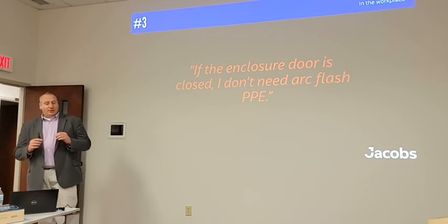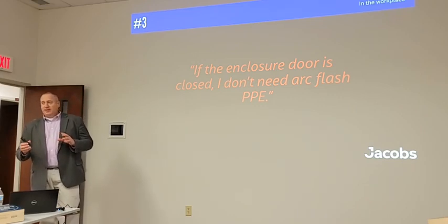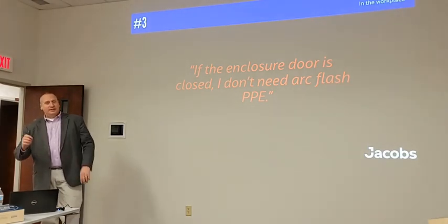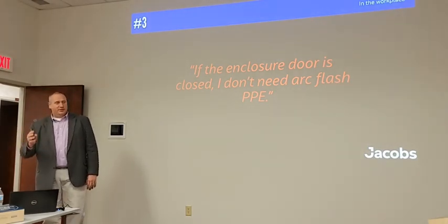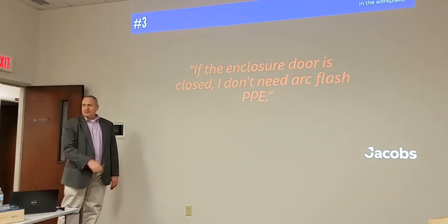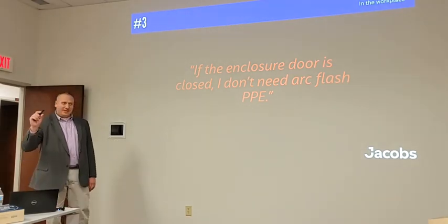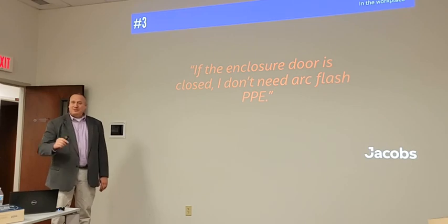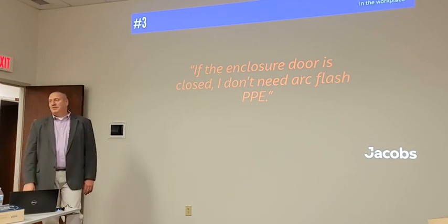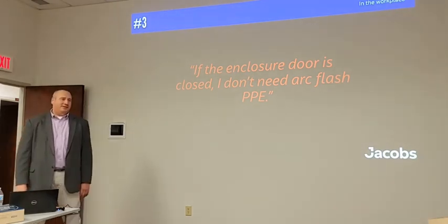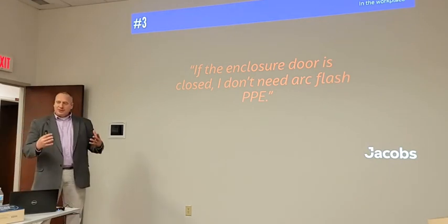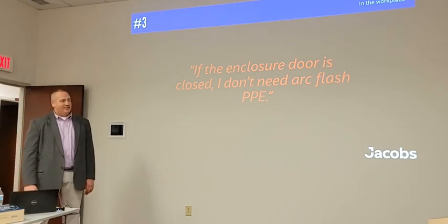And for the older gear that you have to unbolt or unlatch, we all know that when an electrician finishes their task, they bolt everything up, all the bolts, all the latches, before they walk off. No, they do the very least that they have to do, because they know they're going to be back here in another week. We don't want to have to undo all this again, so you just barely put enough latch on it to keep it closed under good circumstances, much less an arc flash event.